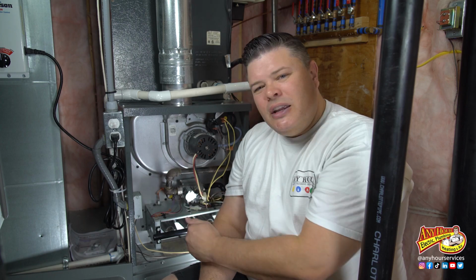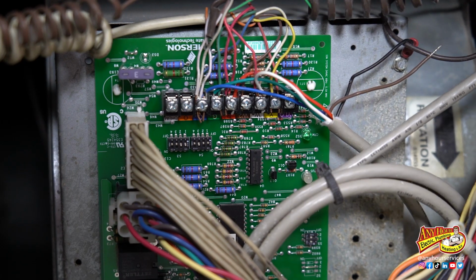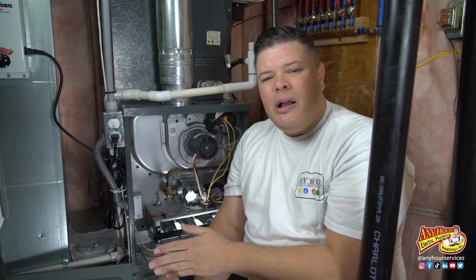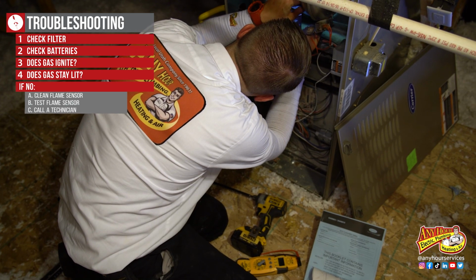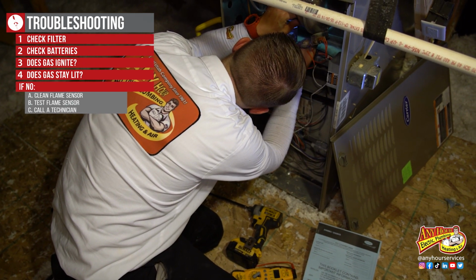Now, if you've tested it, you've cleaned it, and you're still having issues where the flame cuts out after it ignites, it's possible that you've got an issue with the circuit board. And at this point, you start to get beyond the basic troubleshooting that the average person can do. And you may want to have an HVAC technician or company come out that you trust and actually troubleshoot and diagnose the system.